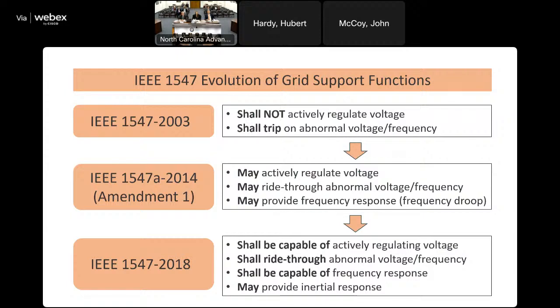In order to make sure the system was safe and reliable in those days, they basically said we don't want these sites actively regulating voltage. And if there's any kind of disturbance on the system, we want them to trip off as quickly as possible. We don't want them to continue feeding into a system fault or anything like that.